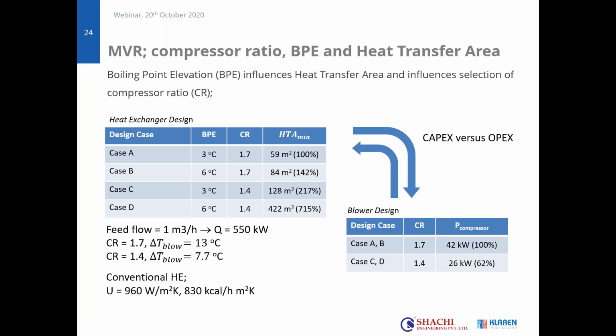So that means that the heat transfer area is really dependent on this combination between boiling point elevation and compressor ratio. As I said, of course, compressor ratio is linked to energy use. So we go to the right bottom table. In case A and B, I have a compressor ratio of 1.7. And that means that the energy that I need to drive my compressor is around 42 kilowatts. If I go to a compressor ratio of 1.4, this compressor energy has reduced to 26 kilowatts. So that's of course beneficial, because the fewer kilowatts that you need means that you need less electricity, and that's less money that you spend on electricity.